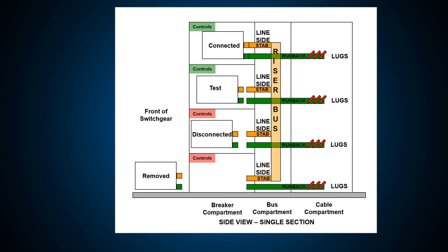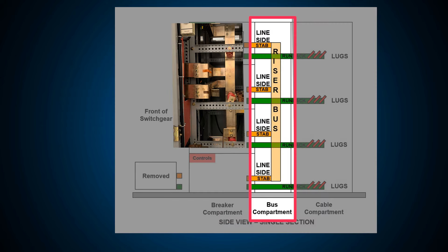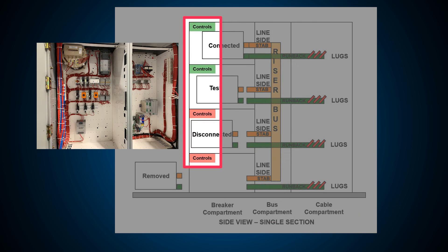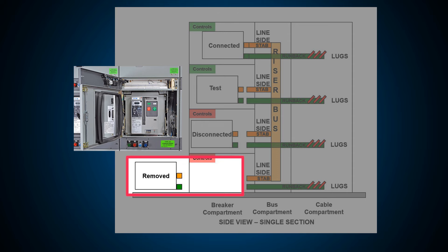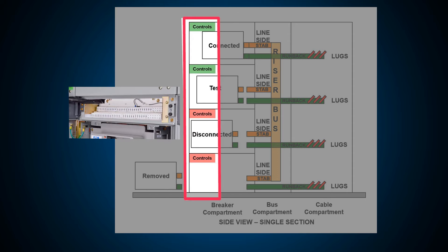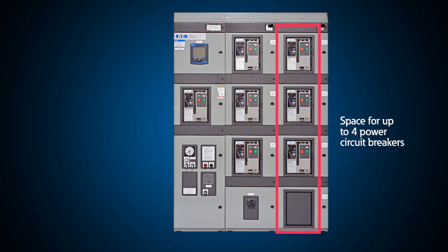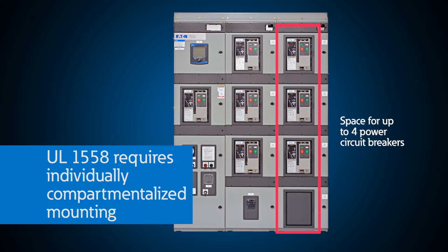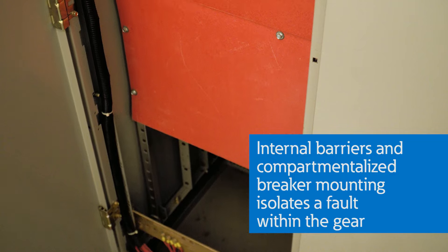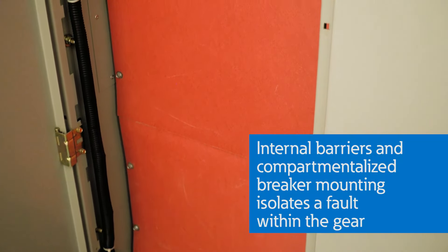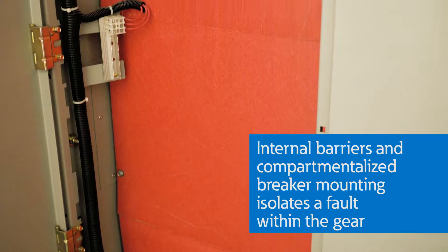Now let's discuss the main parts of low voltage switchgear: breaker compartment or cell, bus compartment, cable compartment, metering control or instrumentation compartment, power circuit breakers, and secondary or control power wiring compartment. Each breaker section can normally hold up to four power circuit breakers arranged in a vertical fashion. UL1558 requires individually compartmentalized mounting — group mounting is not allowed. The advantage of internal barriers and compartmentalized breaker mounting is isolation of a fault within the gear.